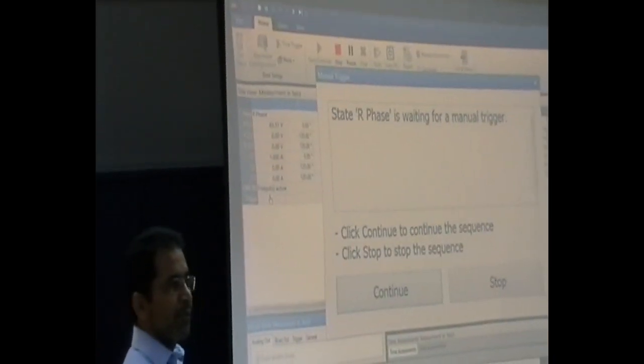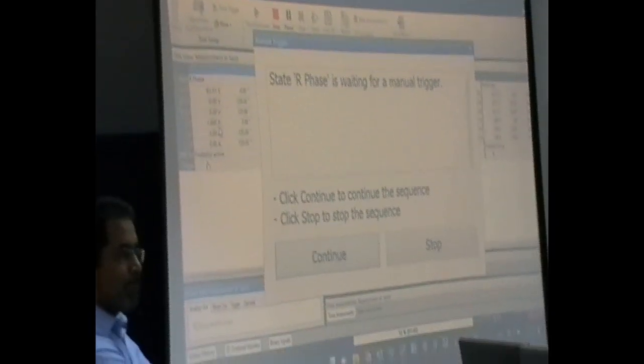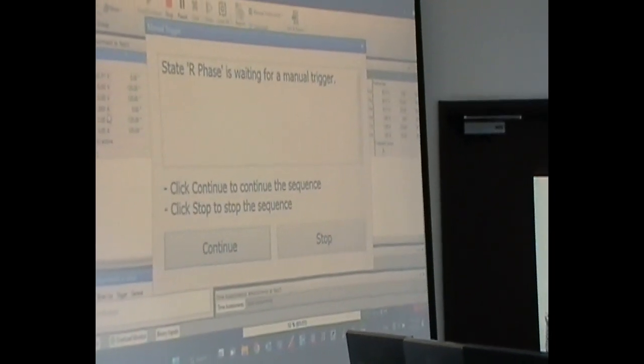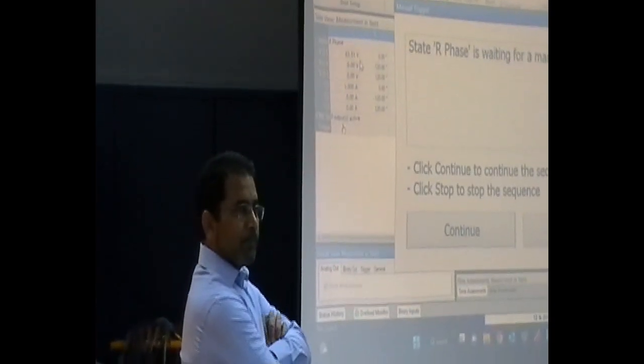We good? Yeah. Students ask, is this from the secondary side? It was read from the secondary side, and it appears as if it's in the primary. So it means that the relay shows that the reading should be in the primary 400, but it receives just 1 ampere because of the ratio. So it just converts through the software to show you that maybe in the primary it's 400. Actually, in the secondary of the relay, you cannot inject 400 here. It's just 1 ampere. The same thing for the voltage from the secondary of the VT. We injected only 1 ampere, but because the CT setting is 400 to 1, we can read it in the relay, either 1 secondary or 400 ampere primary. Again, during testing, you should know that you're injecting in the red phase, you should not get any reading in the yellow and blue phases.